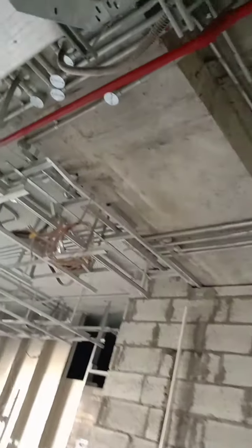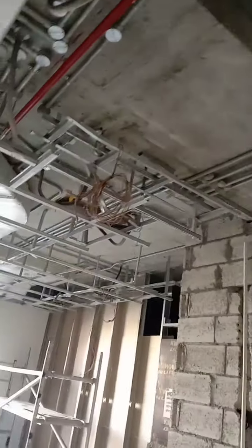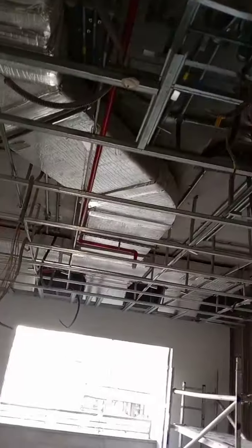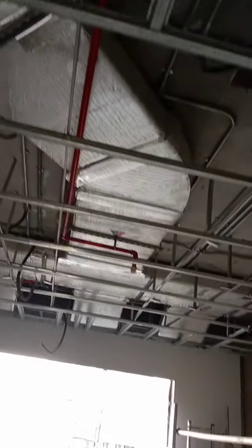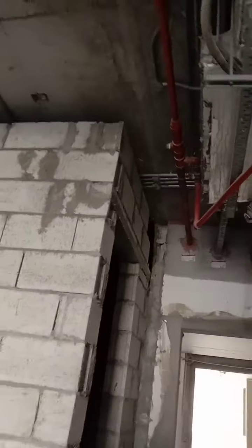We also have to check if we have FCUs installed in this particular location. Ensure that we have power supplying this particular FCU. Provide the specific equipment that is going to control this FCU, be it probably an FCU control panel. In this case, we don't have any FCU control panel, so we will have our isolators that need to be installed. As you can see here, we don't have the FCU yet, so in this room we cannot give clearance for this particular room or for this particular toilet.